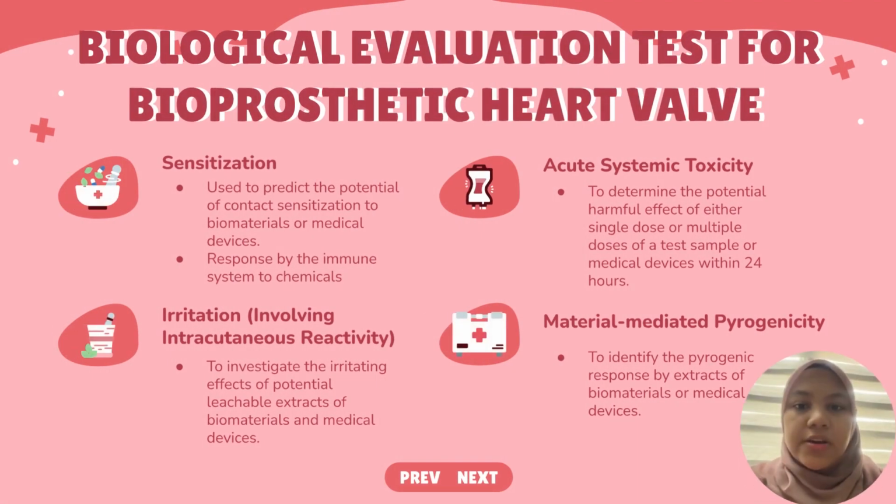The biological tests required for bioprosthetic heart valve are, the first one is sensitization. Sensitization is a response by the immune system to chemicals, and it is used to predict the potential of contact sensitization to biomaterial or medical devices.